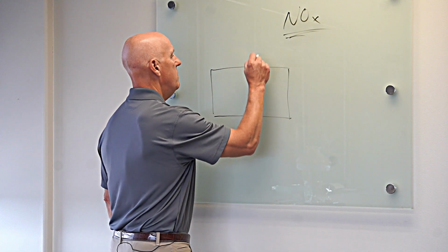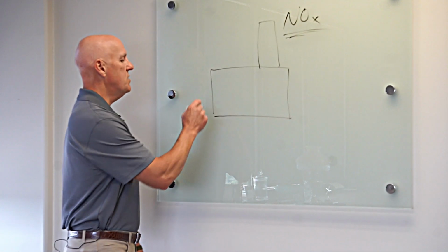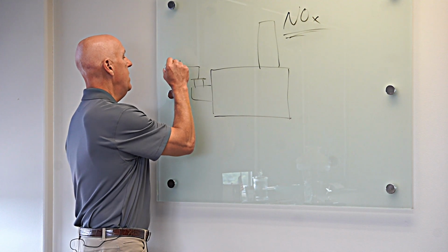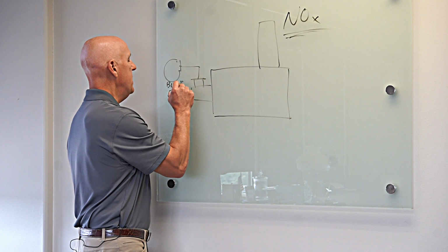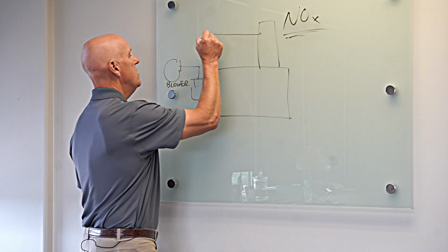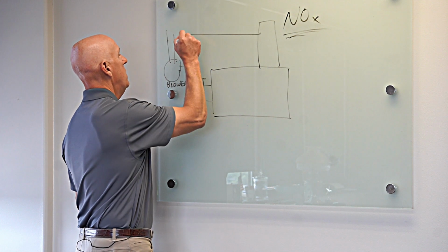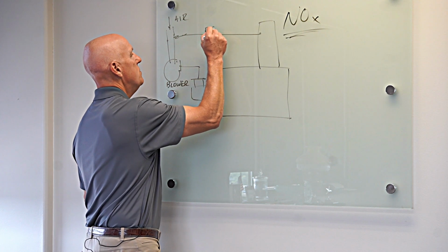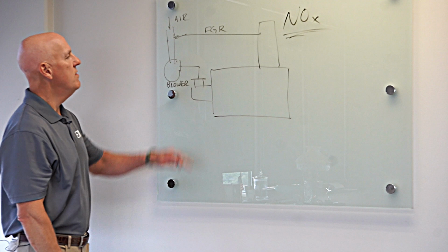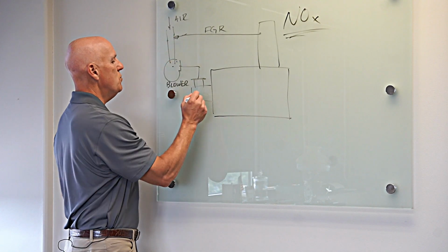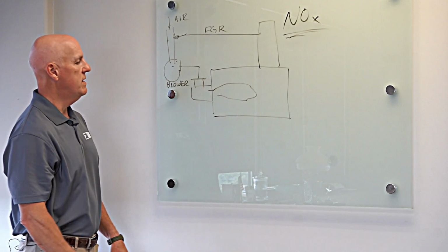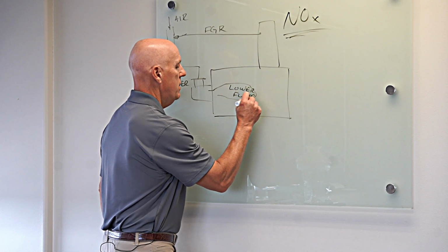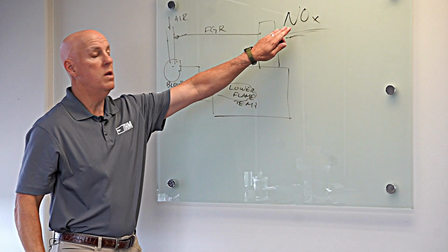One of the ways that we've seen before to reduce NOx is something called external flue gas recirculation, okay? If I have a blower pushing in air, I can take a slipstream off of flue gas. Air comes in here. This is flue gas, FGR, flue gas recirculated. That comes in there, mixes with the blower, and then I get a lower flame temperature, okay? Lowering the flame temperature will lower the NOx levels.